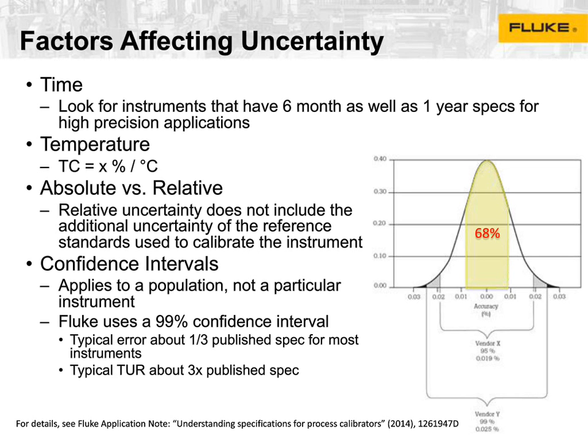Absolute versus relative. A lot of times manufacturers will quote a relative spec. That is, it does not include the equipment that was used to calibrate the gauges. That equipment has uncertainty itself. And basically what happens is whenever you calibrate a gauge, the equipment used to calibrate the gauge is calibrated by something else. And that's calibrated by something else. And it goes all the way back to the National Institute of Standards and Technology, or NIST. And they have the standard, they'll tell you, hey, here's what a PSI is. And so basically, unless you add all of those uncertainties together, you have a relative uncertainty.